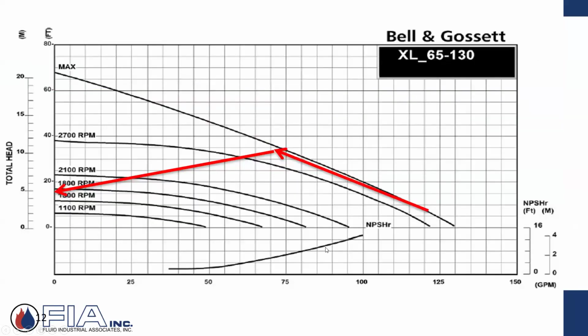What I just want to show you real quick are 2 curves. One right here is a particular model number. It doesn't mean anything to us right now, but it's a pump curve. Here's my maximum speed curve, and here's my set of conditions, maybe at operation. And then I have these various other speed curves. What I'm showing here is that in proportional pressure, as the valves close and I need less flow, this is the curve I'm going to follow. The pump is going to follow in reducing its performance based on speed control as the system conditions require less and less.